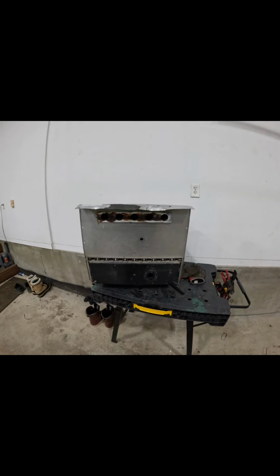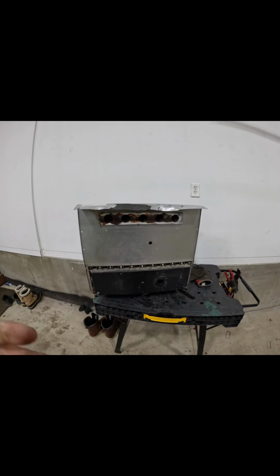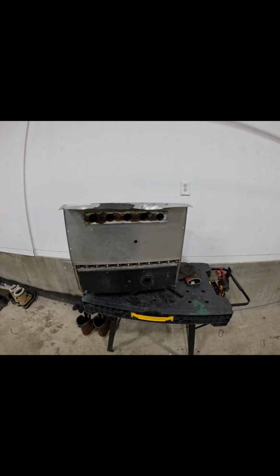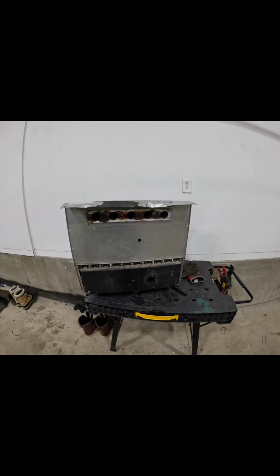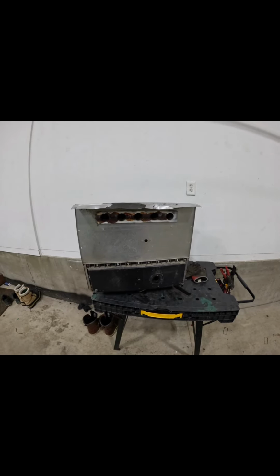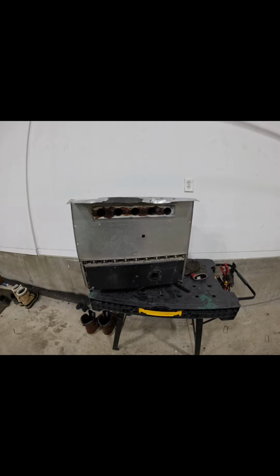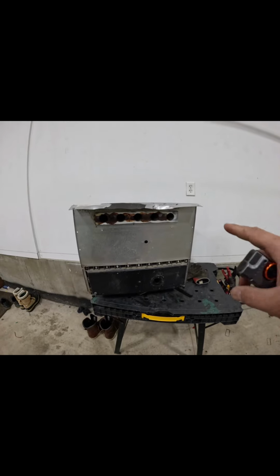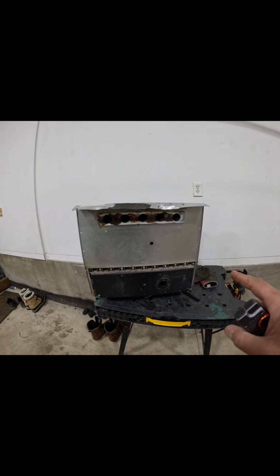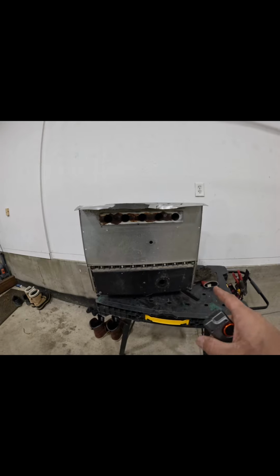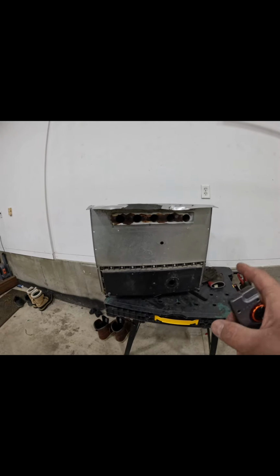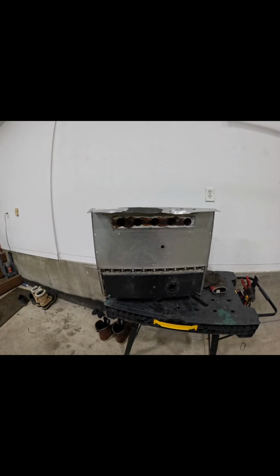So anyway, we're at this stage now - he has a new heat exchanger, it's working great, the flame is fantastic, and we dialed in the gas pressure. Everything is good. So I want to talk a little bit about this unit, and then about what it means when we say a heat exchanger has a plugged secondary heat exchanger.